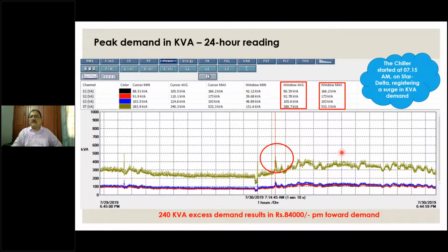So I asked them why this peak has happened. The chiller was started at 7:15 a.m. on star delta, registering a surge in kVA. Similarly, in the afternoon, again the chiller is the largest load. So they admitted that this is the reason why it has happened.